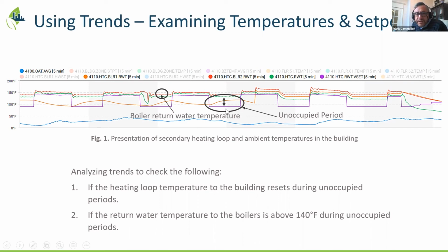Just quickly on the first point, this is the unoccupied periods. The purple line is the set point of the building loop, the water temperature going into the building. The set point does go to 90 degrees, which is great. But the actual temperature of the loop, this green line, you can see that it doesn't. Even though the set point is there, it's not actually happening. So this is how you can use trends to understand if your building is working as intended. Programming is such that the set point does reset, but it's not actually happening.